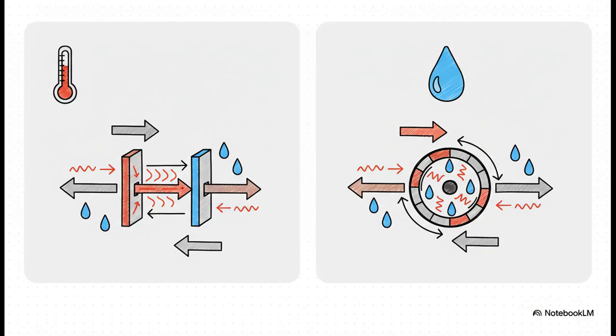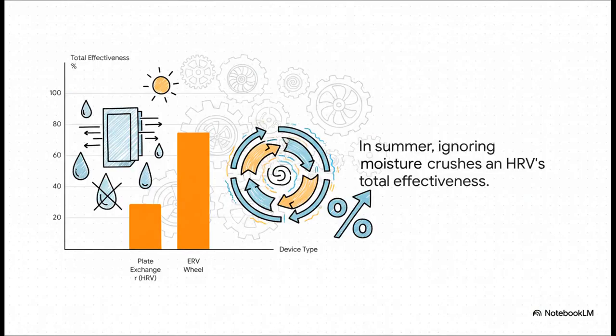And that ability to handle moisture is what separates it from its cousin, the HRV. A standard heat recovery ventilator is a sensible-only device. It moves heat, sure, but not humidity. The ERV, on the other hand, is what's called a total enthalpic device. That's just a fancy way of saying it captures the total energy, both the heat and the humidity, the whole shebang.